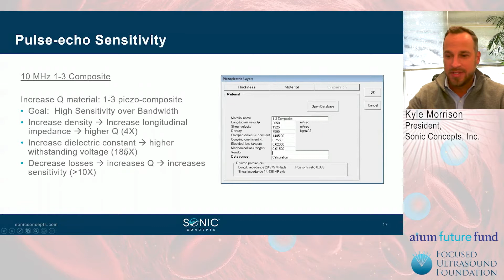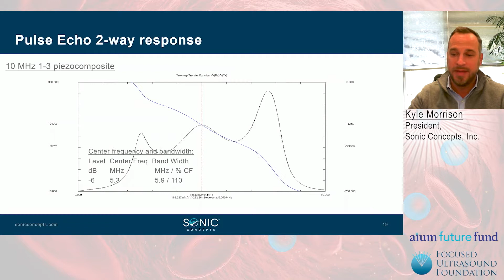So we're using a resonance thickness here on the composite, a quarter wavelength matching layer, and the same rear acoustic loading that we were using for the piezopolymer. So we have good bandwidth for the pulse echo now. We're 12 times the sensitivity of the piezopolymer with reasonable bandwidth.